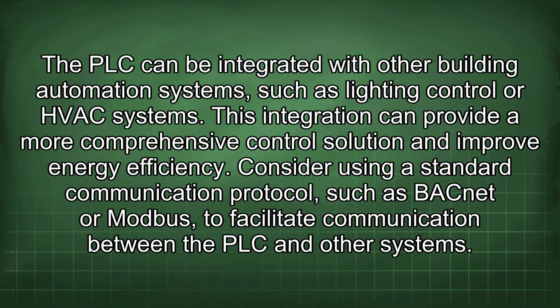The PLC can be integrated with other building automation systems such as lighting control or HVAC systems. This integration can provide a more comprehensive control solution and improve energy efficiency. Consider using a standard communication protocol such as BACnet or Modbus to facilitate communication between the PLC and other systems.